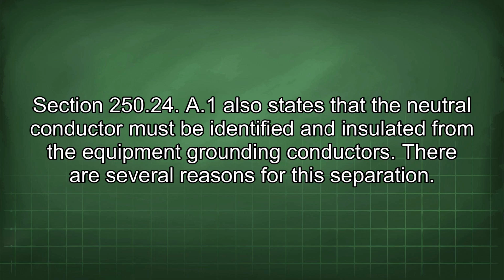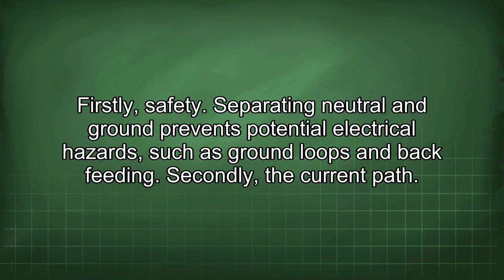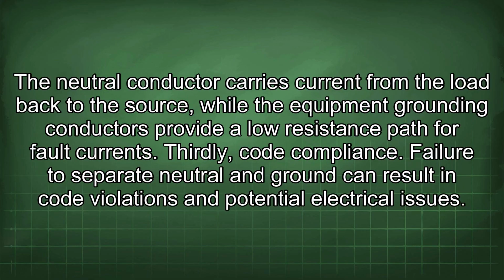There are several reasons for this separation. Firstly, safety. Separating neutral and ground prevents potential electrical hazards such as ground loops and backfeeding. Secondly, the current path. The neutral conductor carries current from the load back to the source, while the equipment grounding conductors provide a low resistance path for fault currents. Thirdly, code compliance. Failure to separate neutral and ground can result in code violations and potential electrical issues.